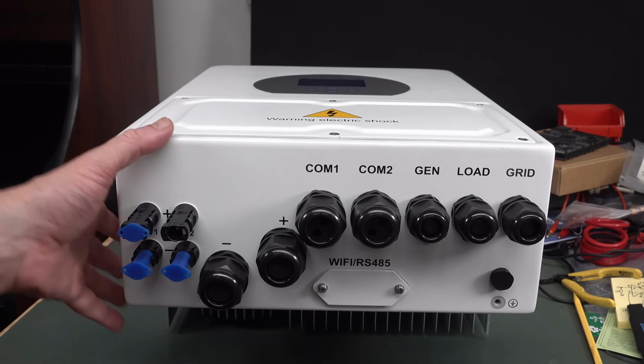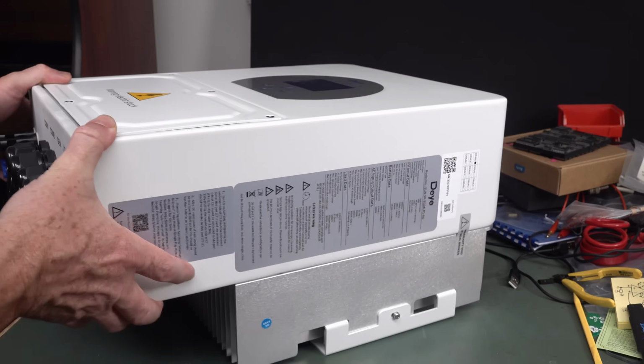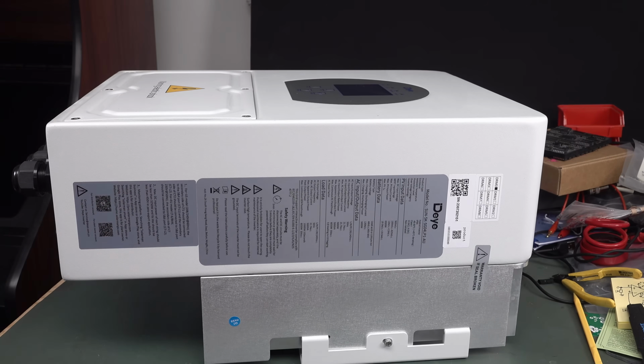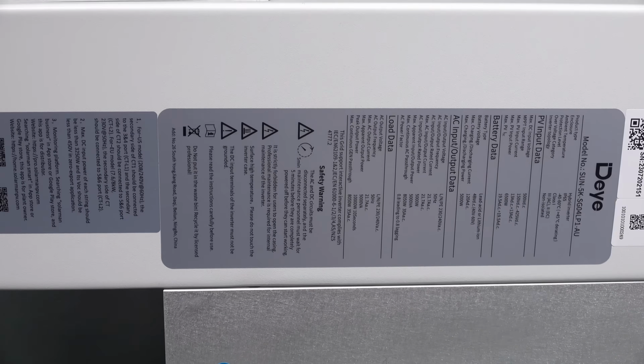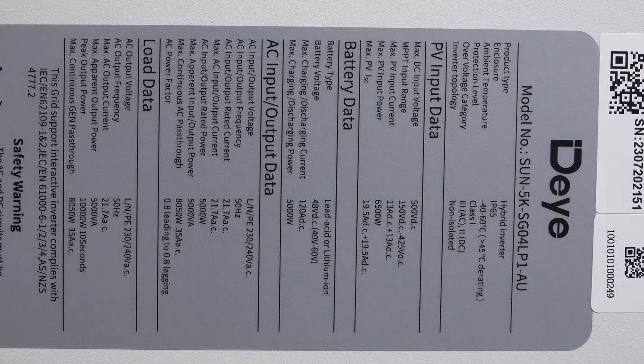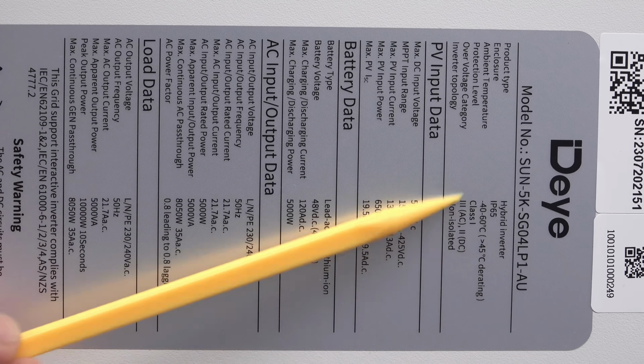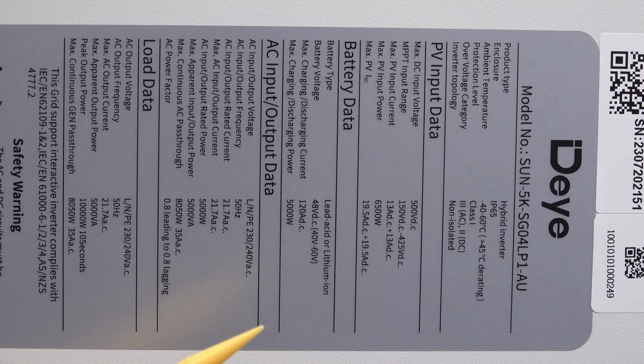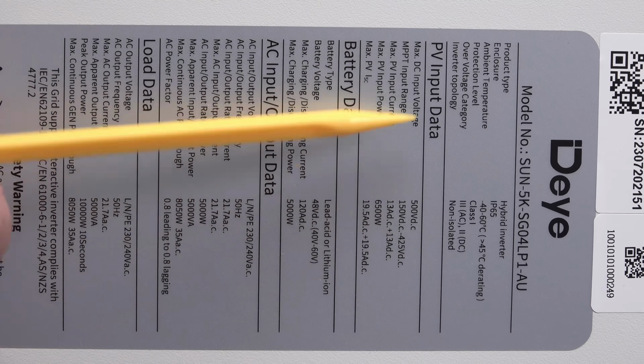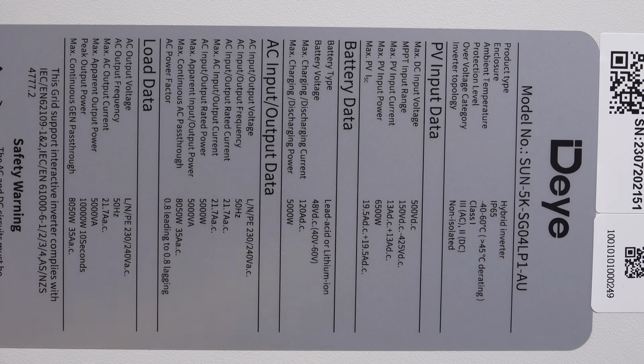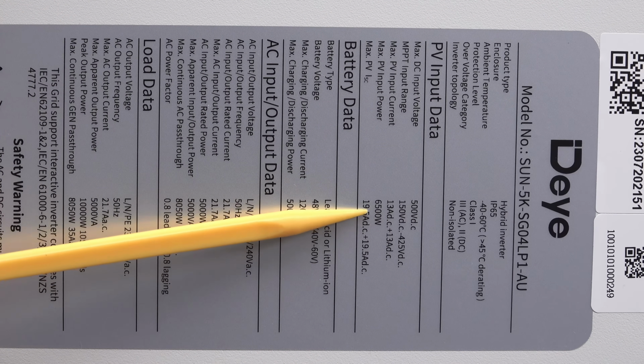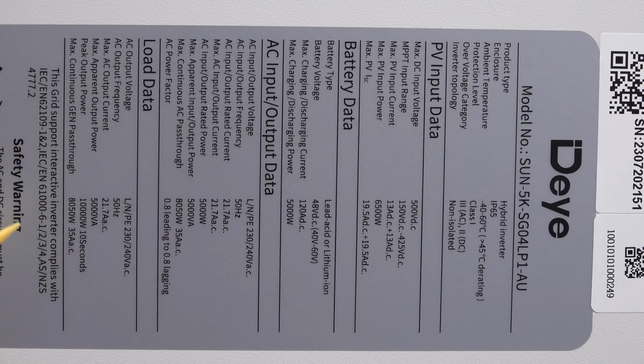Look at this bad boy, it's a bit of a beast. We've got giant heat sinks on it. We'll show you the specs, and you'll have to read them sideways if you're really interested. Anyway, it's a hybrid inverter, IP65, so good enough for outdoor mounting, rain and whatnot. It's a nominal 5 kilowatt inverter, but it can actually do 6,500 watts, 6.5 kilowatts peak.